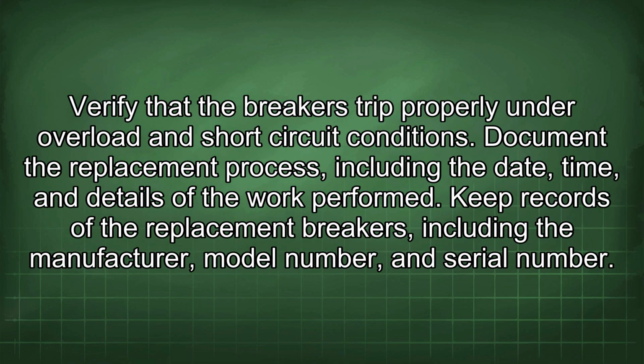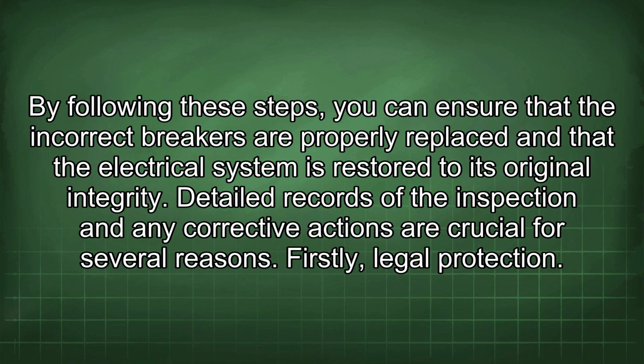Verify that the breakers trip properly under overload and short circuit conditions. Document the replacement process, including the date, time, and details of the work performed. Keep records of the replacement breakers, including the manufacturer, model number, and serial number. By following these steps, you can ensure that the incorrect breakers are properly replaced and that the electrical system is restored to its original integrity.